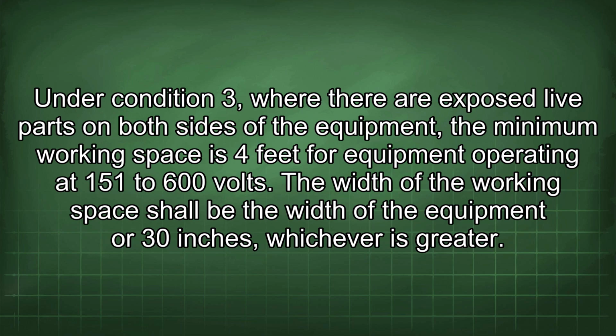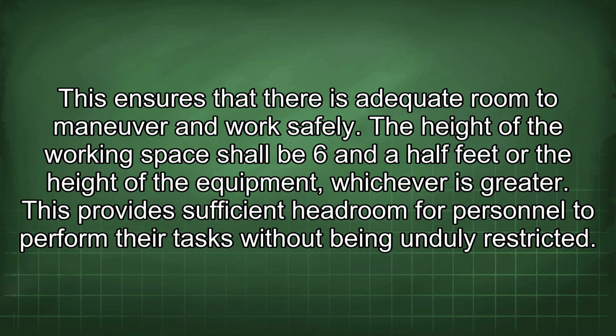The width of the working space shall be the width of the equipment, or 30 inches, whichever is greater. This ensures that there is adequate room to maneuver and work safely. The height of the working space shall be 6.5 feet, or the height of the equipment, whichever is greater. This provides sufficient headroom for personnel to perform their tasks without being unduly restricted.